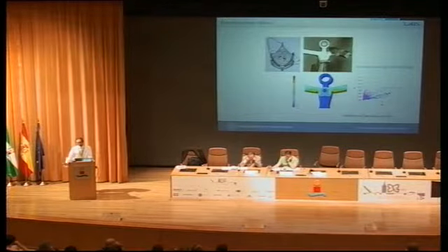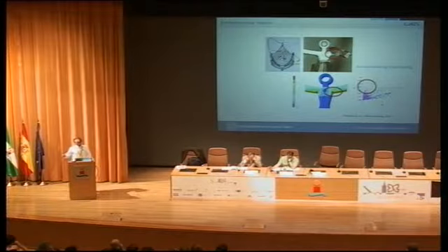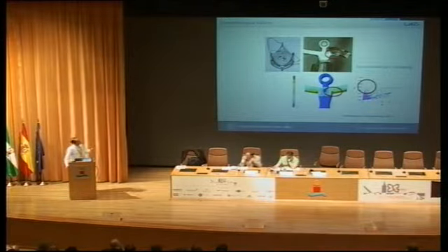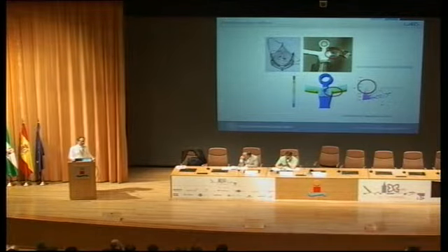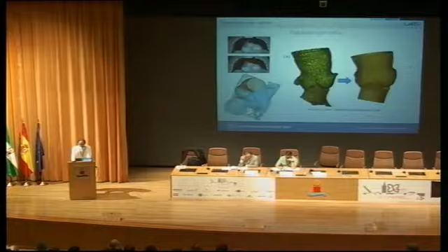And this was observed also in another accelerated test where we applied 150 millimeters of mercury and we observed a fracture. Of course, it's not statistically conclusive, because we didn't do a big campaign. We have just done a couple of tests which confirm that by increasing the gradient, you can have a fracture, and this is also predicted by the in silico simulation.